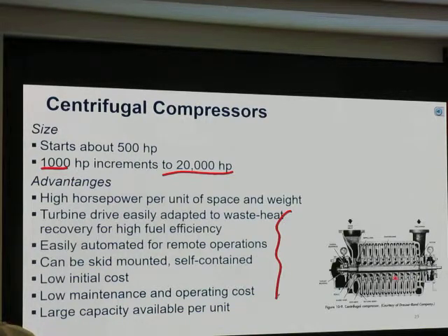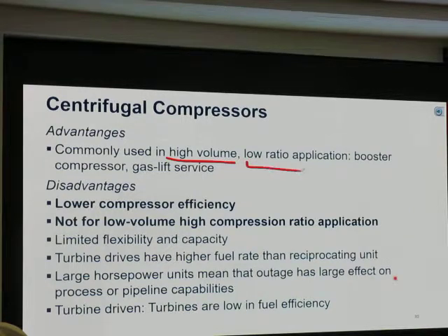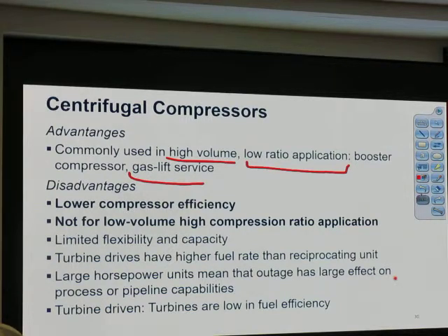Okay, large capacity, it can basically do high volume, so generally it has high volume, low compression ratio. If you don't want to compress it much, but you need high volume, like in gas lift service, we use centrifugal compressor.